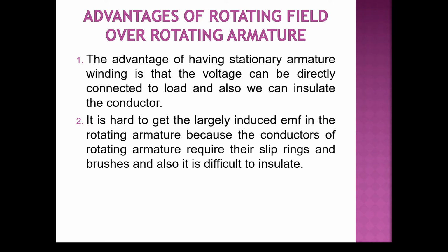So the voltage can be directly connected to the load and we can insulate the conductor easily. This is one of the advantages of having a stationary armature winding. Second one is that it is very hard to get a largely induced EMF in the rotating armature, because conductors of a rotating armature require slip rings and brushes. So it is also difficult to insulate.